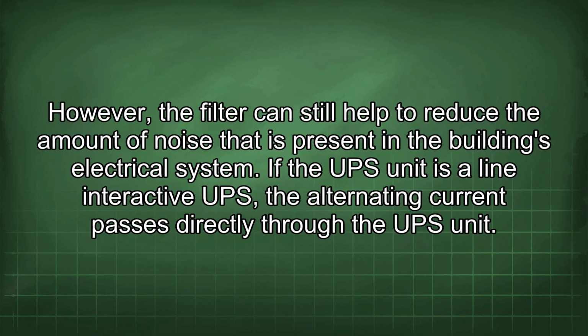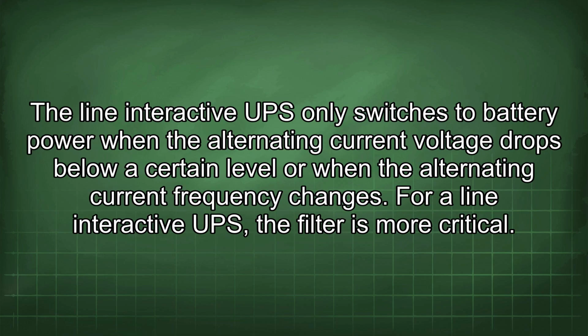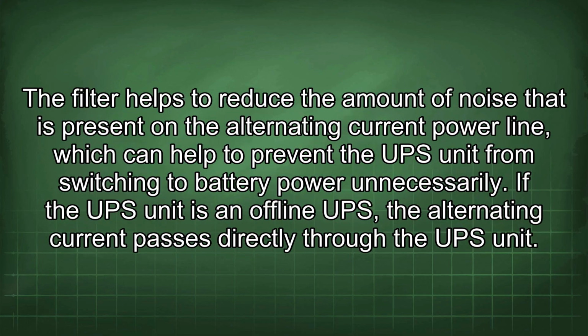If the UPS unit is a line interactive UPS, the alternating current passes directly through the UPS unit. The line interactive UPS only switches to battery power when the alternating current voltage drops below a certain level or when the alternating current frequency changes. For a line interactive UPS, the filter is more critical. The filter helps to reduce the amount of noise that is present on the alternating current power line, which can help to prevent the UPS unit from switching to battery power unnecessarily.